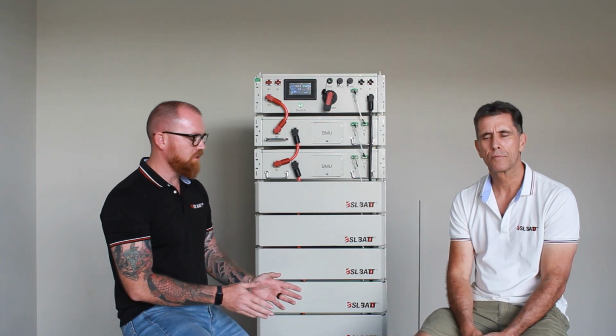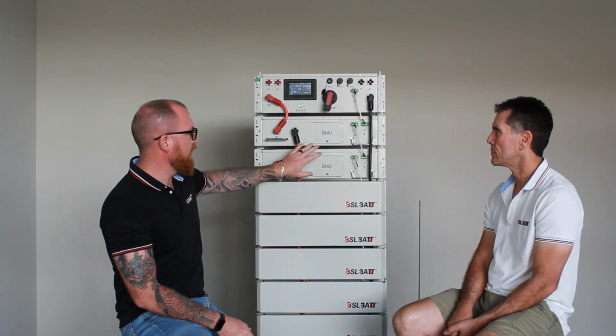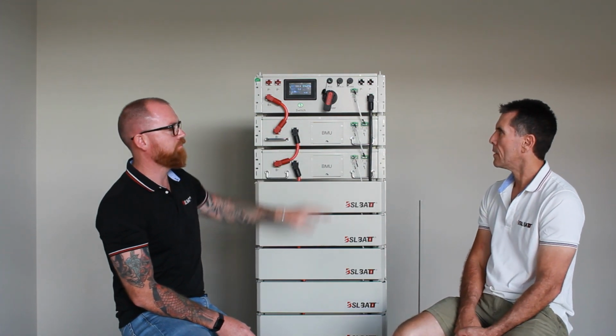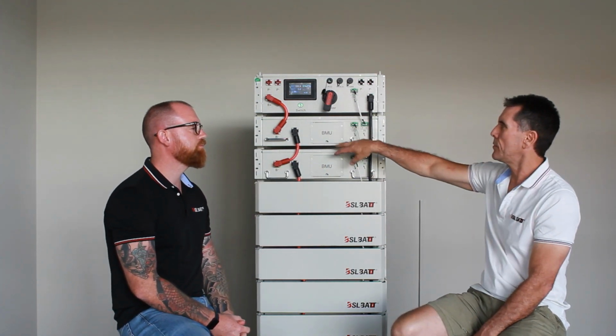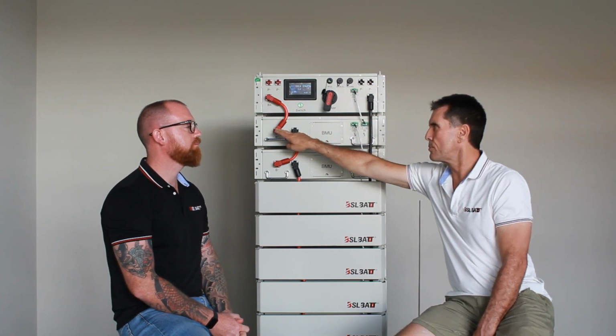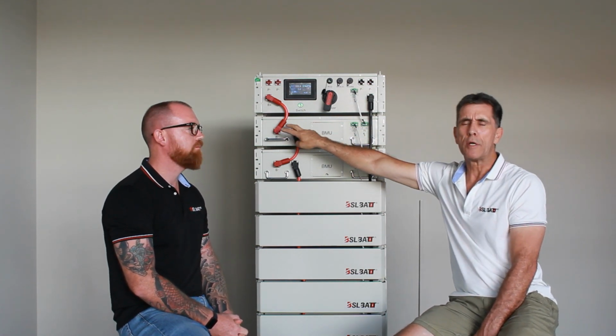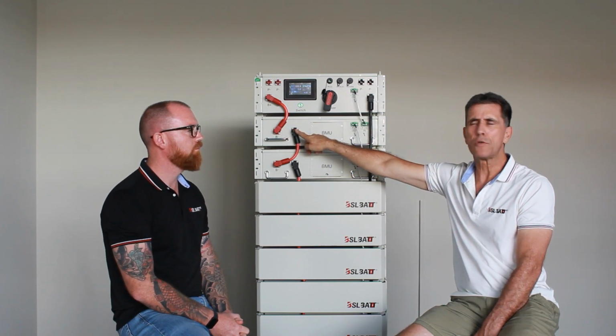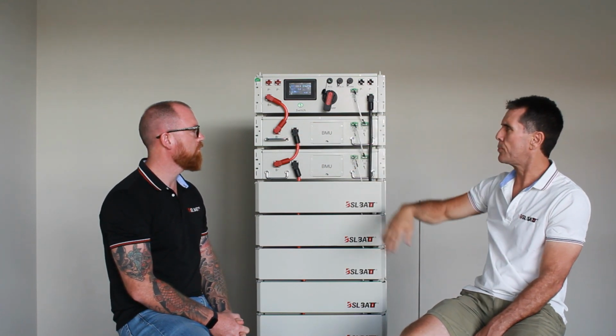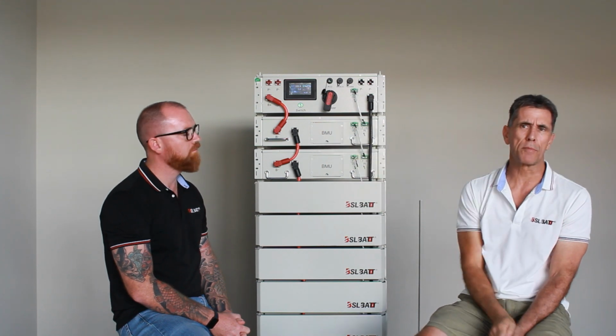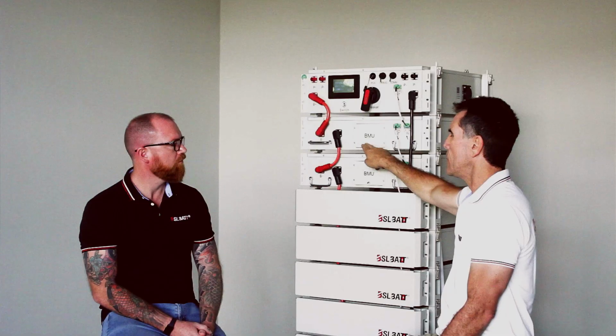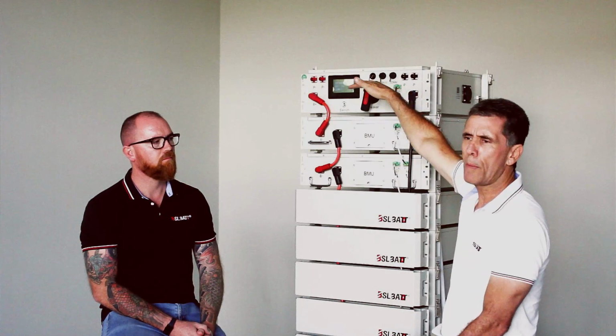So let's just unpack one module quickly - what is in one module? Typically in one block you're going to have 18 cells, with a connection point, positive and negative, and if you measure on there you're going to get about 57 volts. Then it's got your communication board with a built-in BMU, which you can access from the front, so you don't have to take the battery apart. You remove this front cover, you get to the BMU unit, and the BMU just controls the cell voltage, gives data to the BCU unit on top, as well as the temperature, and it does limited passive balancing.